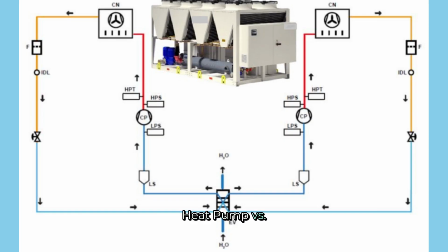Heat pump versus chiller. A chiller produces chilled water by absorbing heat from the building and rejecting it outdoors. Its primary job is cooling. A heat pump, on the other hand, can do both cooling and heating. It uses the same refrigerant circuit as a chiller, but with a reversing valve that can switch the direction of refrigerant flow. This allows the evaporator and condenser to swap roles depending on the mode. So, while the layouts look very similar, the heat pump adds versatility.